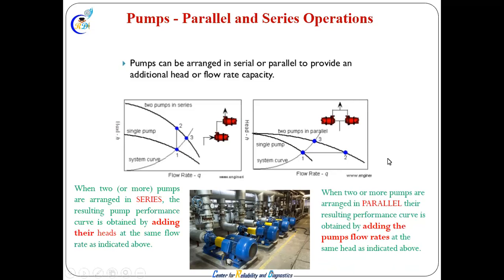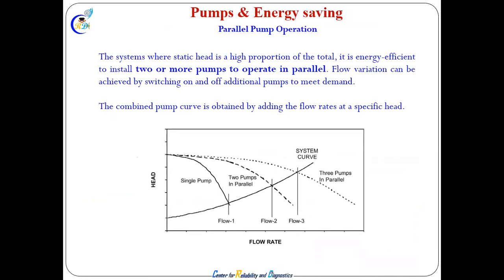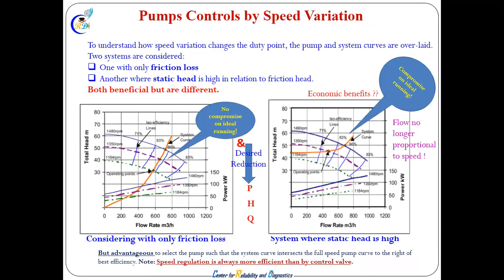And how do we operate for the same system efficiency, or what is efficiency? System efficiency, where will the money go? Maximum to energy. So think about it that way. For parallel operation you can put 2, 3, 4, 5 pumps, but it will look like that. The system is one. You put any number, you can see how much gain you get in the flow. You will not get 2 times, 3 times, 4 times, because your system curve is not changing. Your system resistance, the site condition, is not changing, right? This is all about speed variation and how it takes care of it. In a simple way, I'll show you in the next slide, otherwise it will take time.